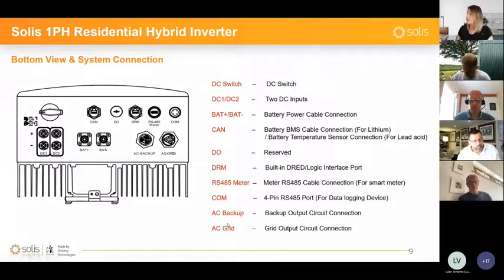And very important, now we have the AC grid connector, which will connect the inverter to the main AC grid. And secondly, we have the AC backup port, which is the wonderful thing about this hybrid inverter, which allows the customer to connect to it all its critical loads that they can then power either during power outages or in case they lose their AC connection, with power coming in, of course, from the PV and from the battery if available.